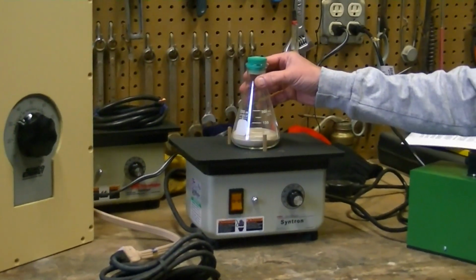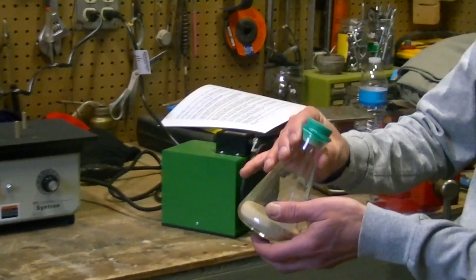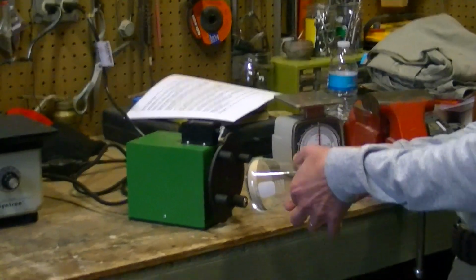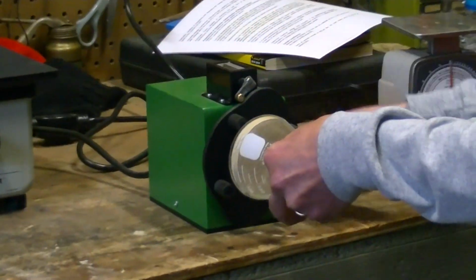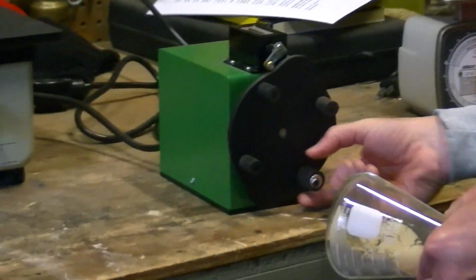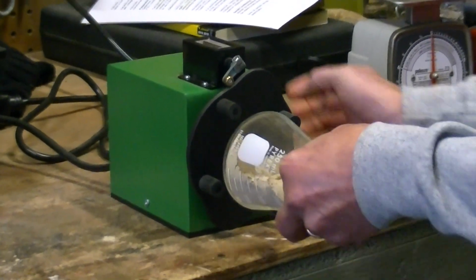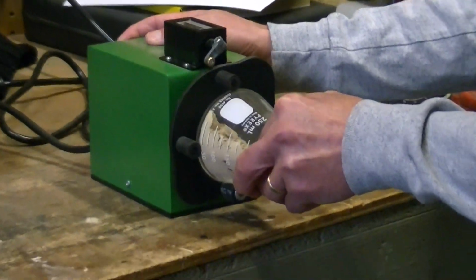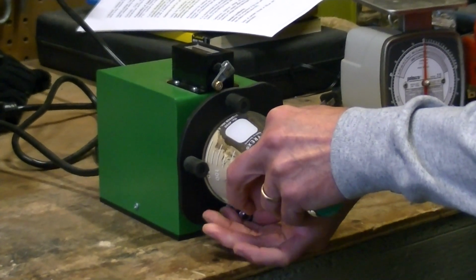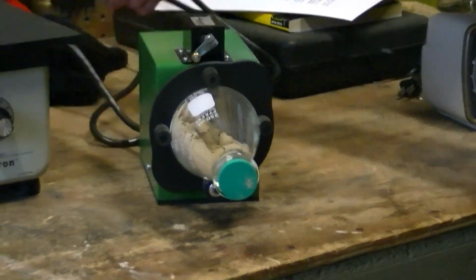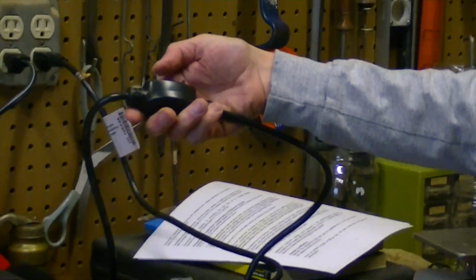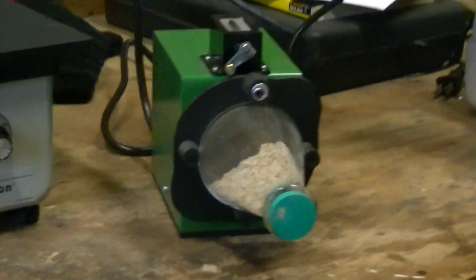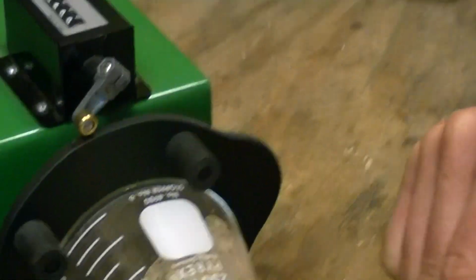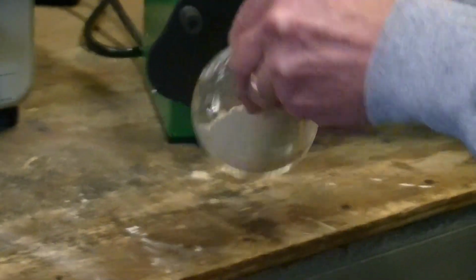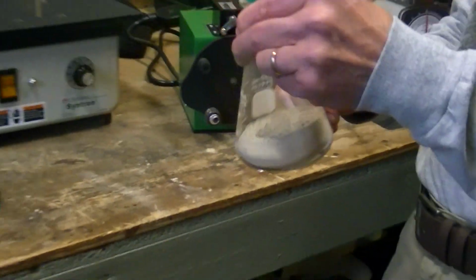Take the sample off, and you're going to hold it very carefully so you don't jar the sample. You're going to turn it sideways, and you're going to put it into the roto tester. And there's a little roller here that, you can see, it's already fell over, that you can adjust to get this in there, and you can tighten it here. And then on the cord there's an on-off switch, and there's a timer up here, a counter, and once it falls over, you're going to record that number. This is a 4, although it already fell over. It just tells me that we don't have a high enough voltage for this particular material here.